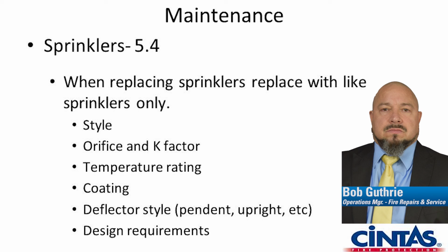In the case of a Central sprinkler, we go back and find the original design criteria for that sprinkler head and match it with another sprinkler head that's on the market, which is possible to do. It just takes some research, and that research has to be done to make sure that the system still functions as it was designed.